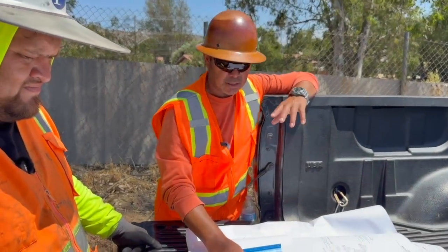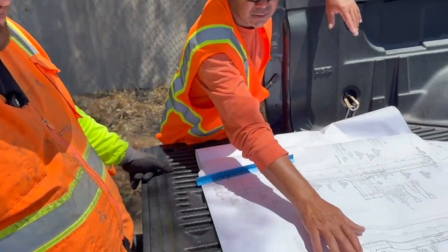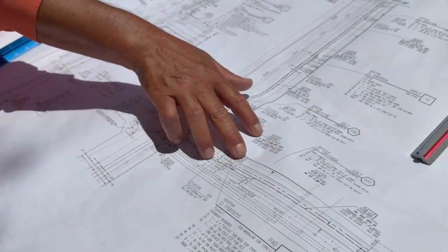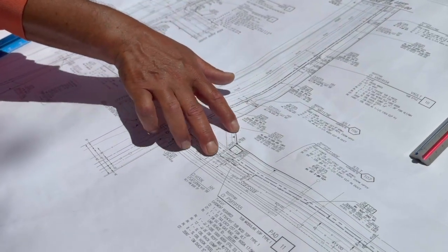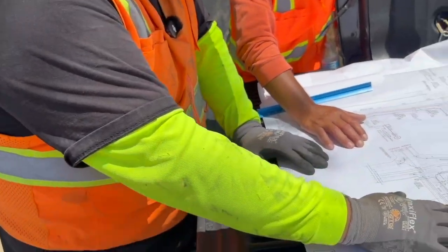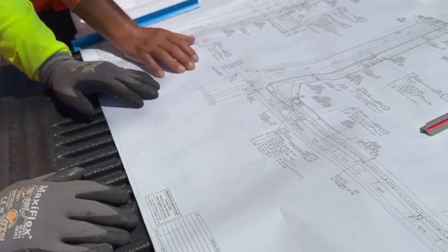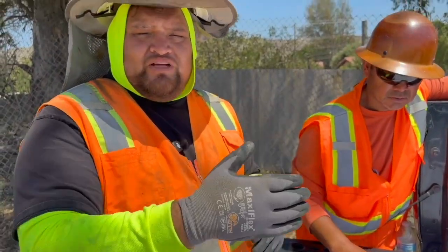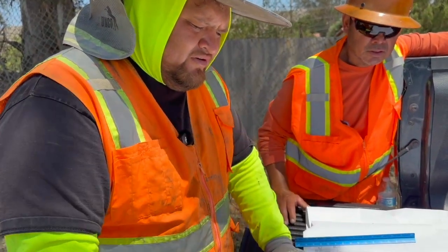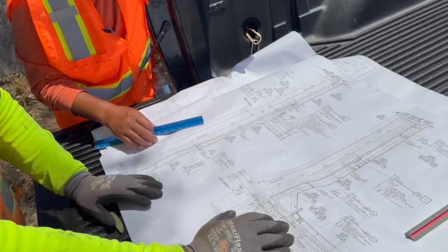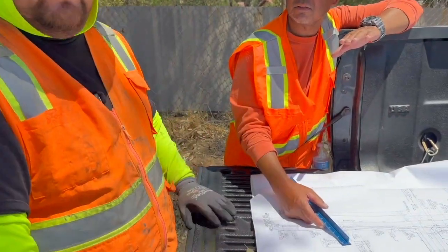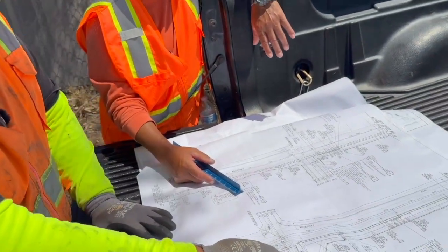I just want to mention, and you can give me a little more information about it, I see the trench kind of turns now, and I see little call outs right here, numbers. What does that mean to you, what are they for, specifically? So these are called angle points. There's some type of sweep that turns, and they're used to turn. So we use that to turn and get into all the boxes in the right position, just the way they call it out here on the plans.